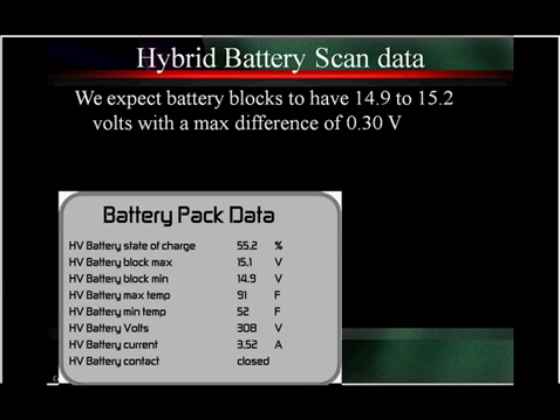We're going to be looking for a 14.9 to 15.2 with a max difference of 0.3 of a volt. Why are we so concerned with a 0.3 volt difference? Here's why: all the cells, all the batteries, all the blocks, however you want to look at it, are all connected in series. All the current to power the motor, all the current to recharge the batteries from regenerative braking or whatever, has to go through each individual battery. If the chemistry is different in one of the batteries, the voltage will not respond the same.